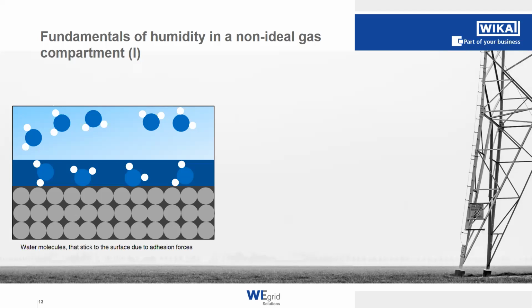Well, that is actually not depending on the energy introduced. It's more depending on the byproducts, like the humidity, which is creeping into the SF6, which is causing no full reconstruction of it. Or for example, when you have the energy introduced into your switch, there could be very fine metal particles which can get loose from the switch, and therefore the metal reacts with the SF6 and therefore it cannot fully recombine itself. Okay, does that answer your question? So pure SF6 can always regenerate itself, but the byproducts like the humidity, or for example the metal from the switch, can cause the SF6 to not fully regenerate itself.